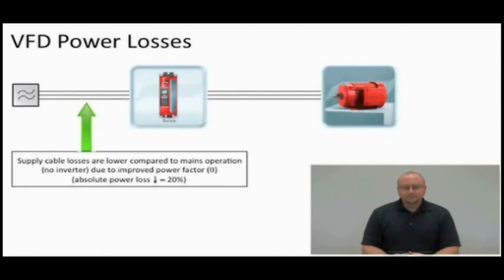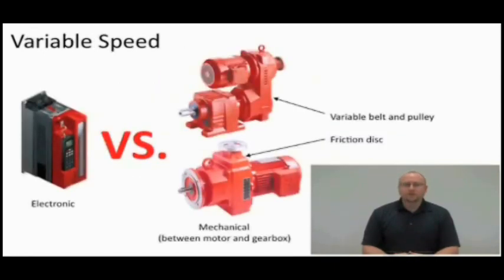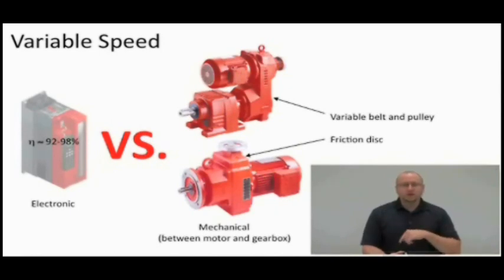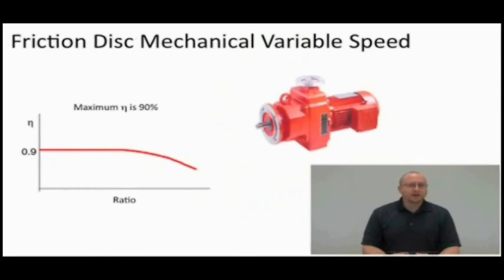And just to compare an inverter to mechanical variable speed control real quick, because there's a lot of people out there that don't use inverters. They have a friction disc type of variable speed control or a belt and pulley system. These are common mechanical ways to change the speed of the system. Remember, an inverter was about 92 to 98% efficiency, so we'll compare that to mechanical variable speed real quick. Actually, the maximum efficiency you can get out of a mechanical variable speed friction disc is 90%. As you change the ratio, as your ratio goes up and the output speed goes down, your efficiency drops off. So the maximum you can get is 90%. That's less efficient than an inverter right off the bat, no matter what you do.